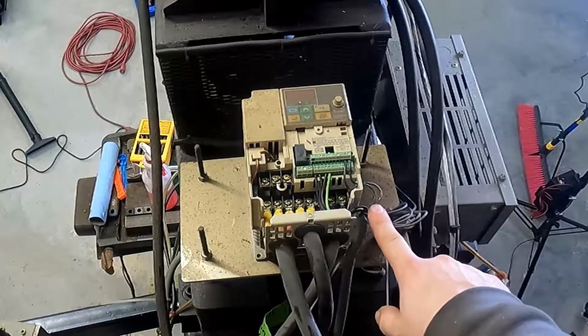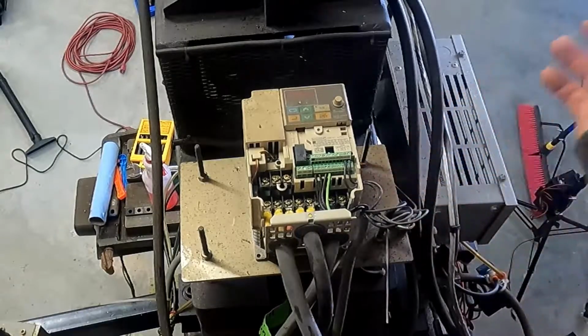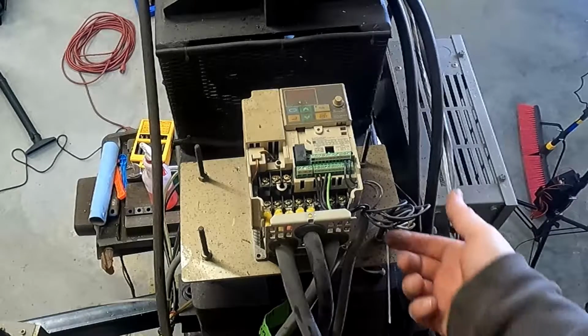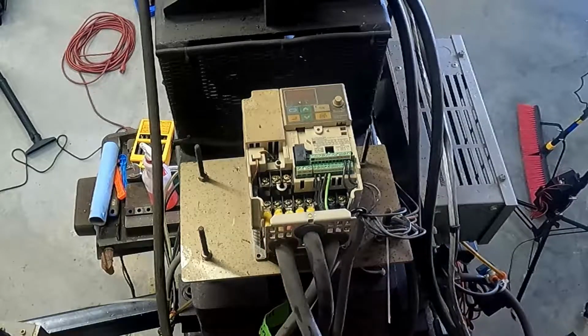This is also a weird way, because this wire should kind of go through there or around there and not kind of through the side of the plastic. And also it shouldn't be doing other stuff. I don't love it, and there's a lot of heat shrink solder joints in this. What I suspect is that somebody bought this cabinet, the big cabinet below we've been looking in, from Centroid, gave it to their maintenance guy, gave him the machine and said, hey, make it happen. What's the worst that could happen? And it worked, but it could be a lot nicer.